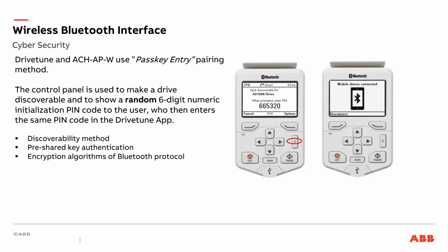Now let's discuss how we create the connection to the drive's control panel and the app, and the security surrounding it. The Bluetooth on the control panel is not active unless a user pushes the question mark key on the keypad for 3 seconds. This activates the Bluetooth on the control panel and makes it discoverable. When this is selected, a random 6-digit number will appear on the screen of the control panel. This 6-digit authentication code must be used with the Drivetune app for there to be a successful connection to the drive. There are encrypted algorithms in the Bluetooth protocol for security.